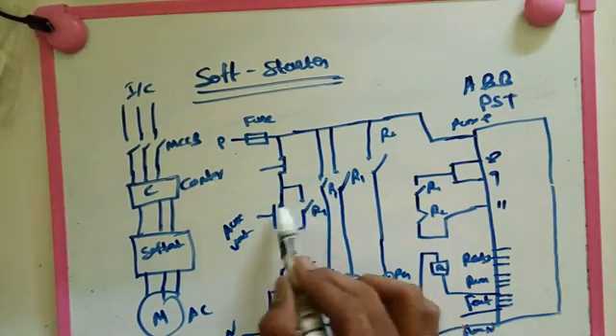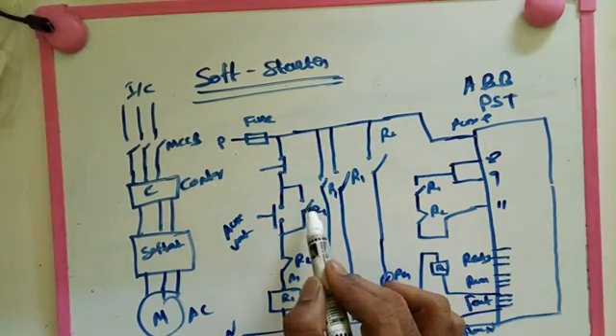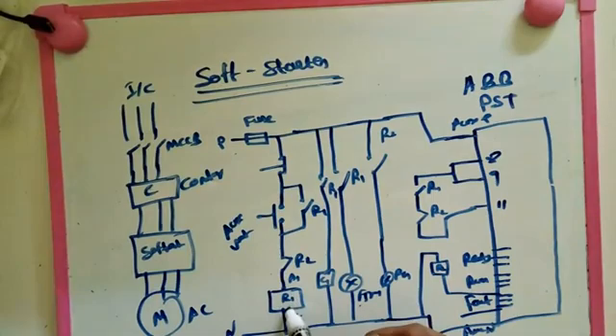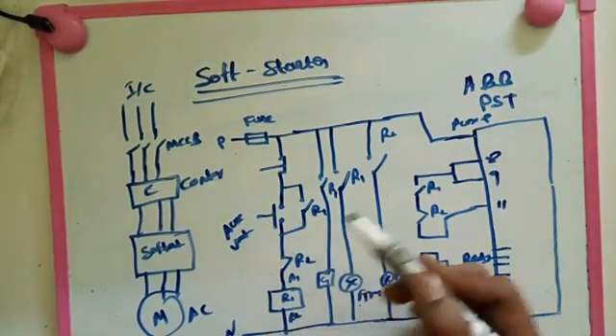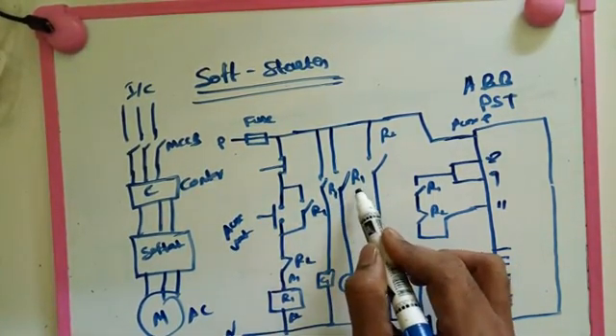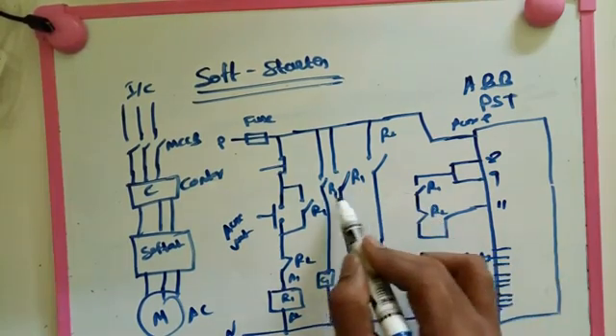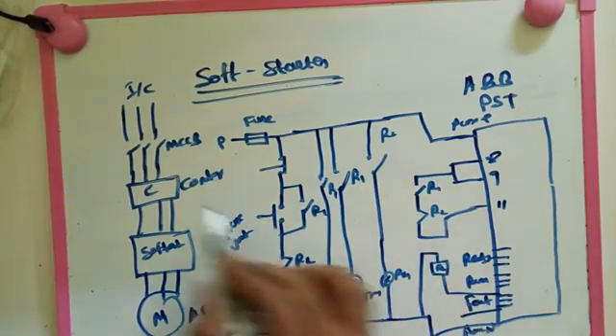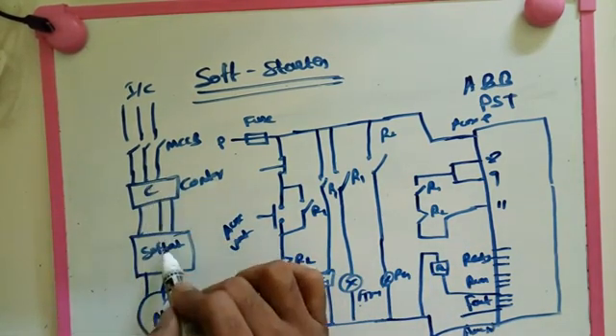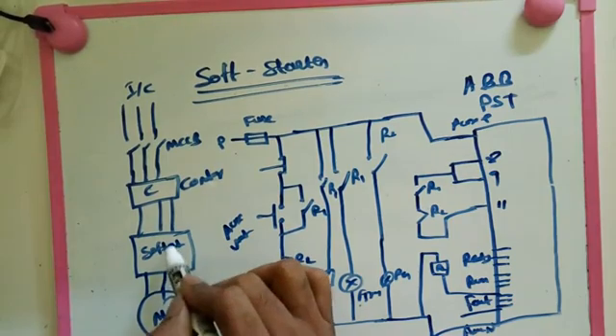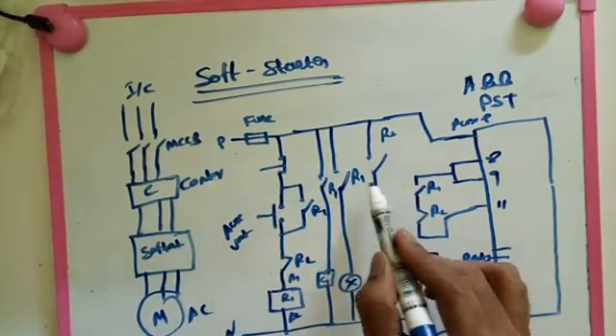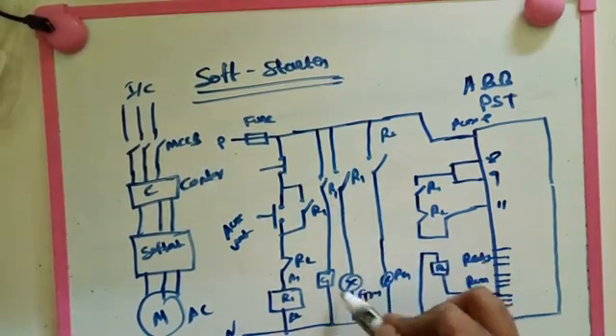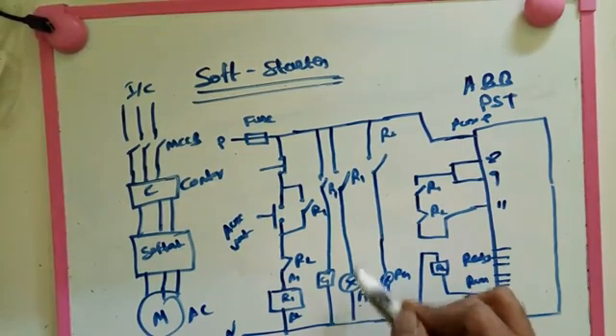After that we got R1 is energized. Then R1 NO is closed. R1 NO is closed, that's why we got R1 always energized. At this time, the three R1 coils are energized and closed. This one is closed, the C1 contactor is energized, giving supply to soft starter. After that giving supply to motor. Here, another one R1 is closed, at that time the green lamp is glowed for running symbol.